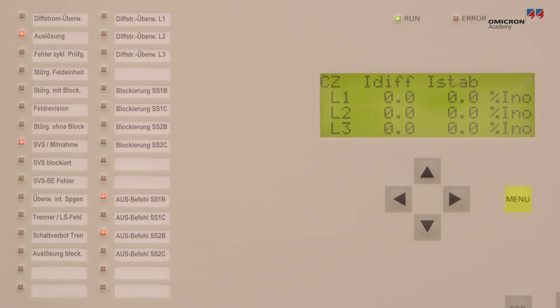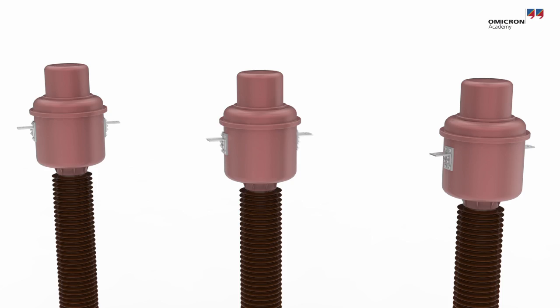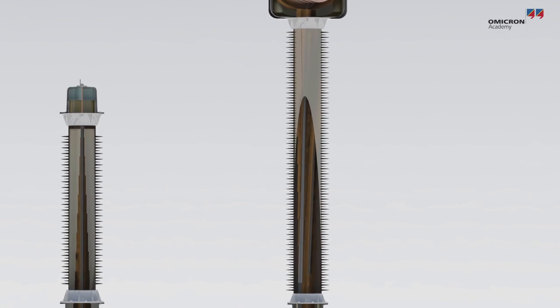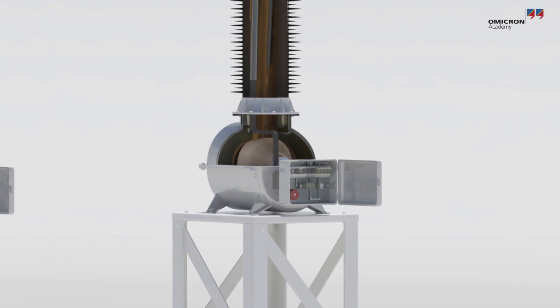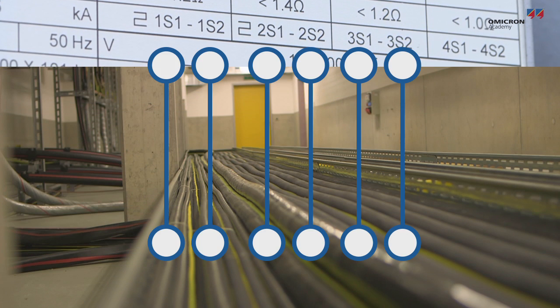Polarity faults can lead to a protection system malfunction. There can be many reasons for improper polarity: the CT might have been installed with the wrong mechanical orientation, a CT could have an internal wiring error, or a single instrument transformer's secondary wires may have been crossed somewhere along the way to the secondary system.